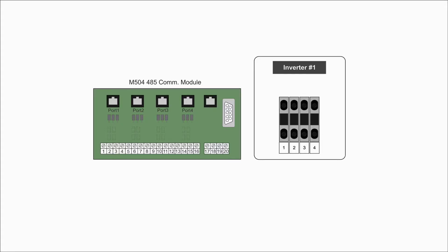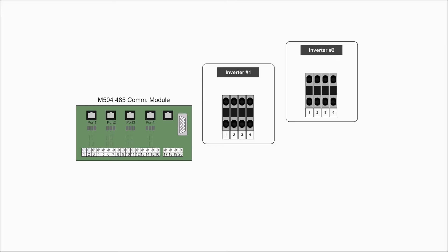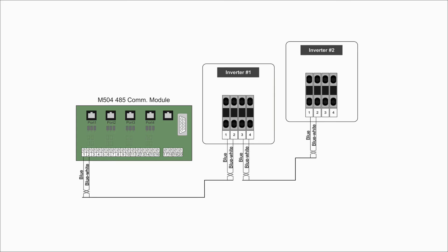To connect the first inverter, wire a twisted pair from the M504 485 COM module terminals D-plus and D-minus to the inverter's A-IN and B-IN terminals. For all successive inverters, wire a twisted pair from the A-OUT and B-OUT terminal blocks of the inverter that is already connected to the A-IN and B-IN terminals of the inverter being added. The M504 gateway will use these connections to communicate with the inverters.